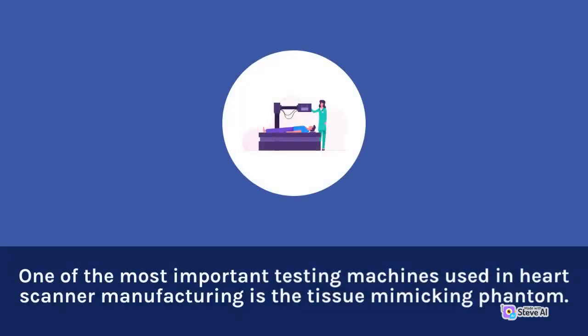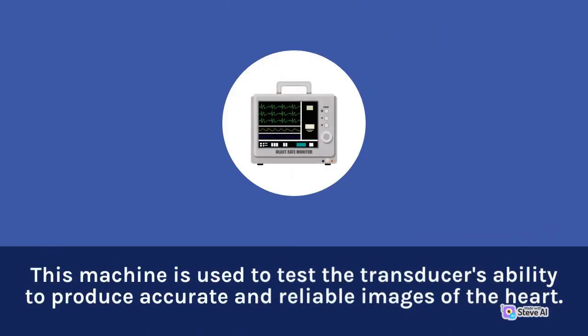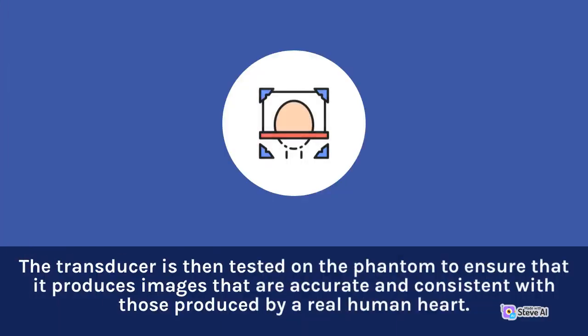One of the most important testing machines used in heart scanner manufacturing is the tissue mimicking phantom. This machine is used to test the transducer's ability to produce accurate and reliable images of the heart. The phantom is designed to mimic the properties of human tissue, including its acoustic and elastic properties. The transducer is then tested on the phantom to ensure that it produces images that are accurate and consistent with those produced by a real human heart.